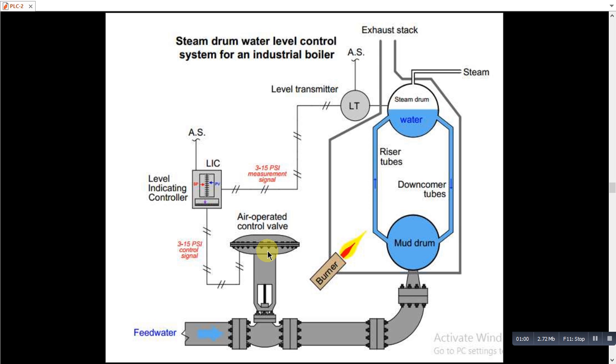So this LT, this full loop, LT level controller and the level control valve, feed water control valve, will then control the level of water in the drum.